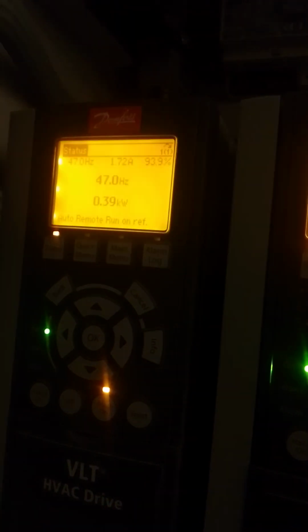As you can see, the pressure or the demand is lower, so the frequency is down. The set point for the frequency, as you can see, for this one which is off is 50. Set point is 50 at 100%. So this one is running at 47, 46. So this is 2. All these are for the control in the panel.